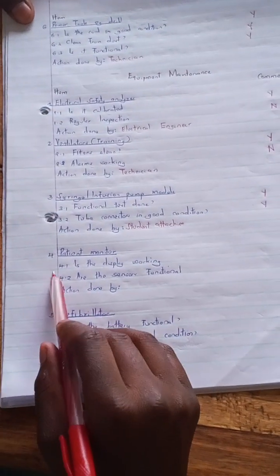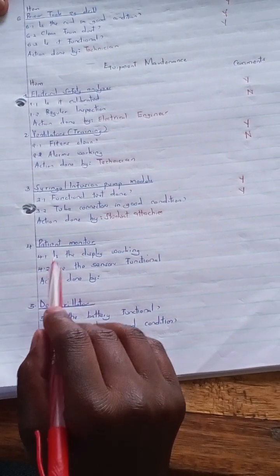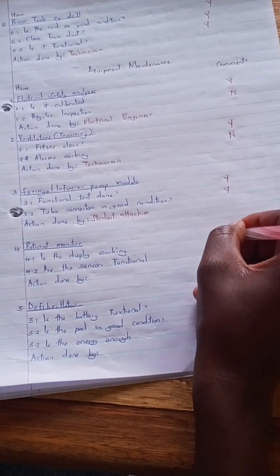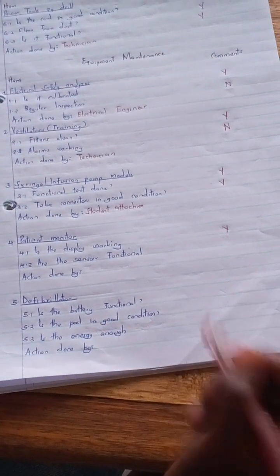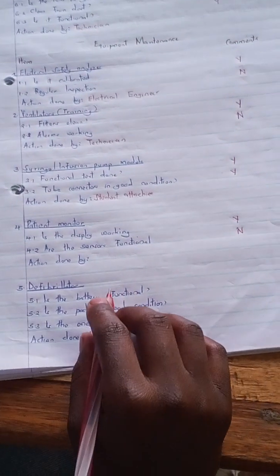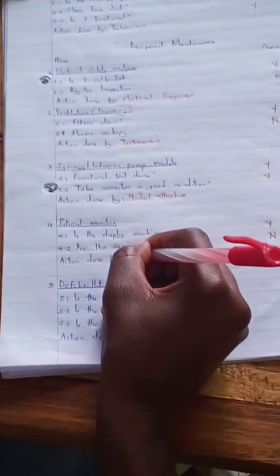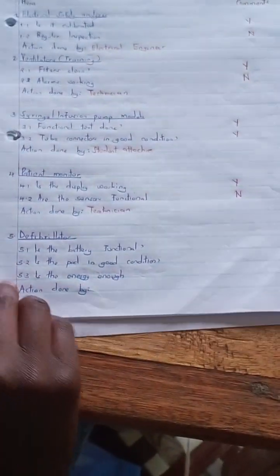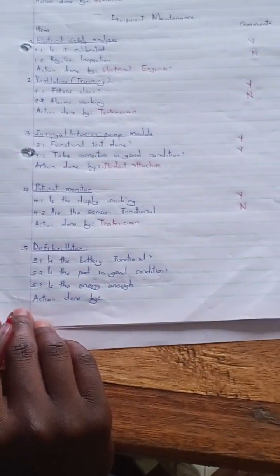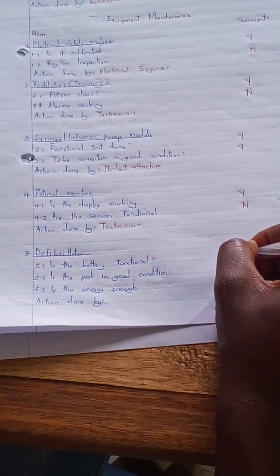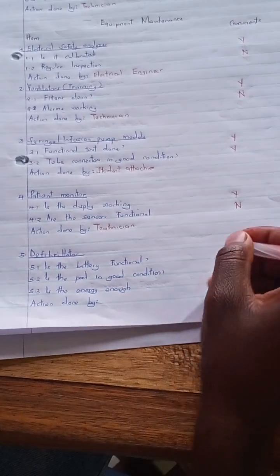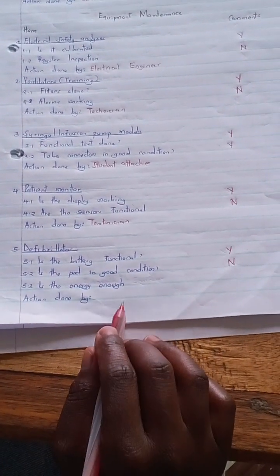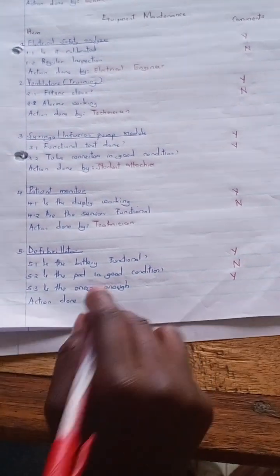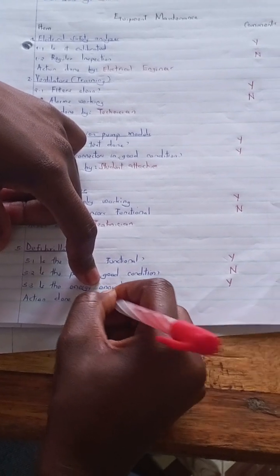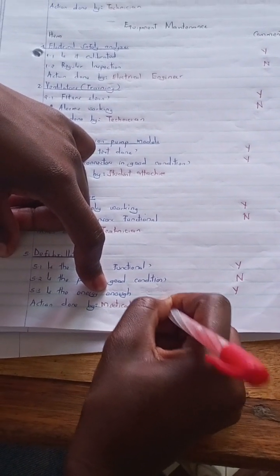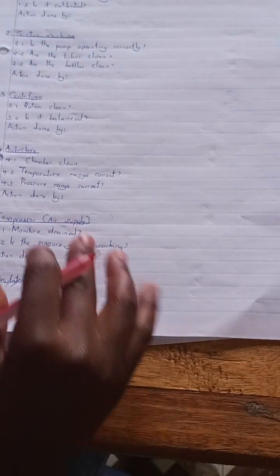Then the equipment number 4 is the patient monitor. Is the display working? When it's working, we will say yes in our comment. Are the sensors functional? When the sensors are not functional, we'll say no. Action done by a technician. Then we'll go to our equipment number 5. That's defibrillators. Is the battery functioning? Yes. Is the pad in good condition? Let's say it's not in good condition. Is the energy enough? Yes. The action done by medical engineer.